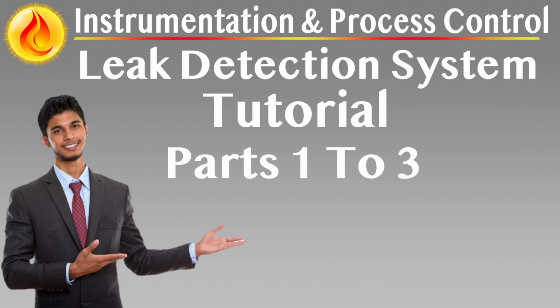Sensitivity is the measure of how small a leak the LDS can detect and how quickly it can do so. It is typically expressed as a combination of minimum detectable leak size and the corresponding response time. While high sensitivity allows for early detection of even minor leaks, overly aggressive settings can increase false alarm rates. A balance must be struck between sensitivity and operational practicality, especially in pipelines with fluctuating flow or pressure conditions.